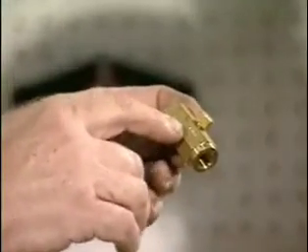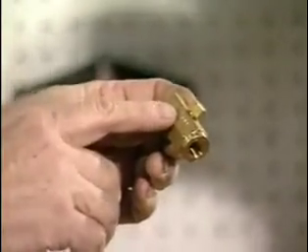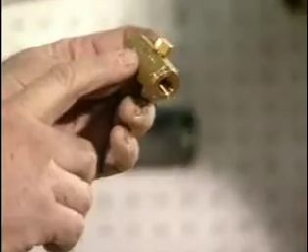Your check valves break that system up. There's an arrow placed on every check valve that Ansul sends with their system. It shows the direction of flow. This, put in backwards, will stop the system from activating.